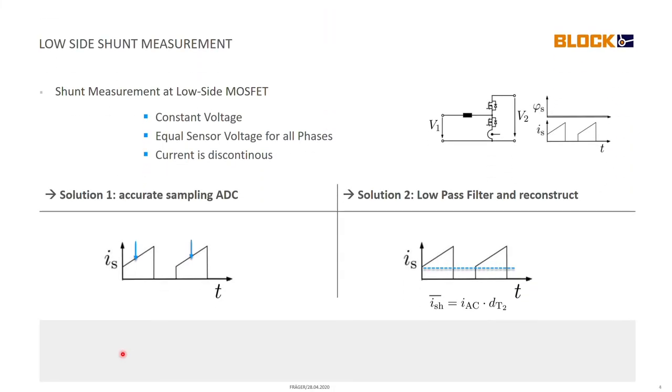This is the concept that I want to present to you today: to do the shunt measurement at the low side MOSFET of a half-bridge circuit. An inverter pretty much consists of three half-bridge cells so it makes sense to first of all look at the shunt or the current measurement for one half-bridge of this inverter.